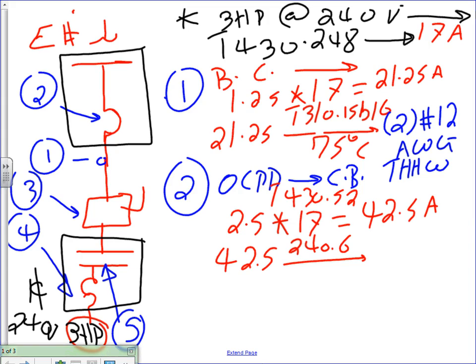Okay, so what did we say, that 45 amp circuit breaker. Now I want you to look at a number 12 protected by 45. Have you lost your mind, Chad? What happened to the small conductor rules that number 12 cannot be protected more than 20 amps? Exception, motors. Can you have this? You can't believe how many people ask this question all the time. Okay, 45 amp circuit breaker. So my circuit breakers will be 45. Let's keep going. 1, 2, 3.